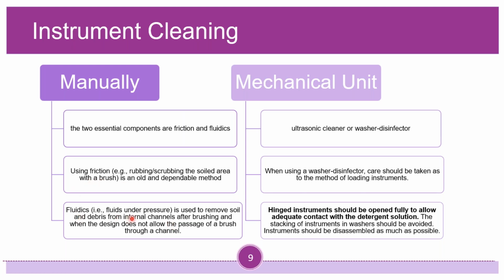So yes, fluids under pressure, fluidics, is used to remove soil and debris from internal channels after brushing, and when the design does not allow the passage of a brush through a channel. That's why you have to use that high pressure, because a brush may be too big to fit into those really, really tiny channels.